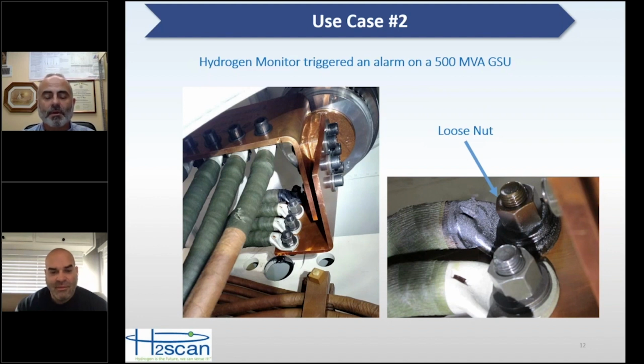So the nice thing here is the hydrogen monitor actually saved that transformer. This probably would have gone into a complete failure, and they would have had to replace the transformer. Okay, so I'm not sure what a 500 MVA transformer goes for these days, but I'm sure they were very happy not to have to go through the trouble of replacing it, much less the expense.